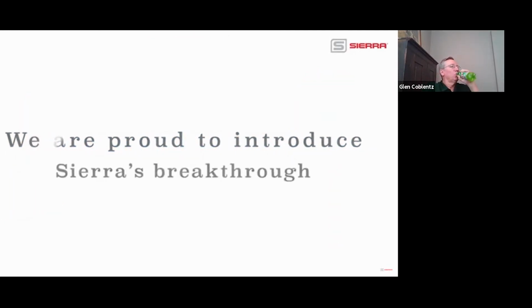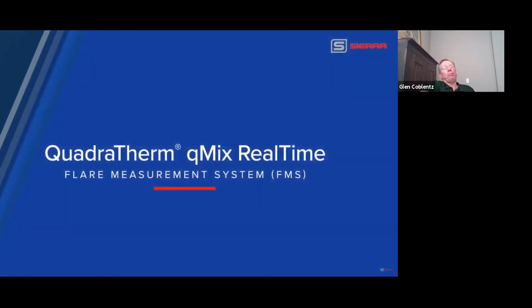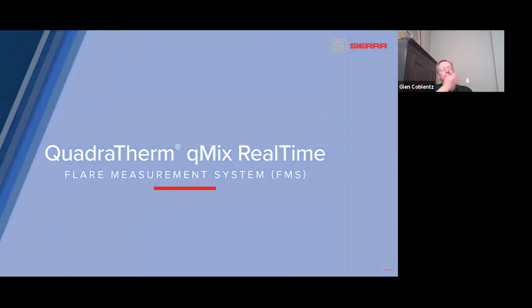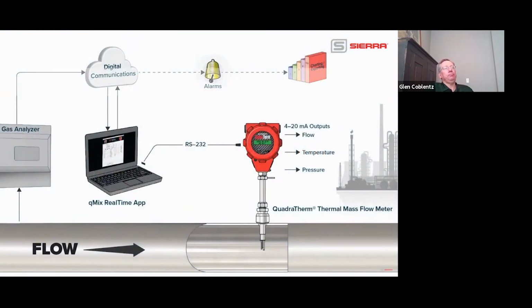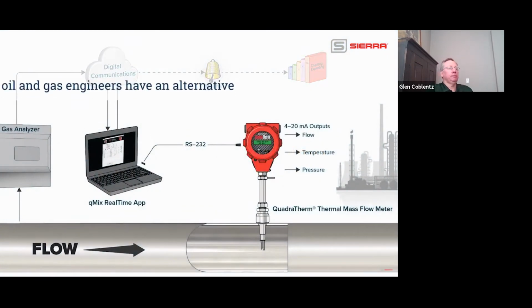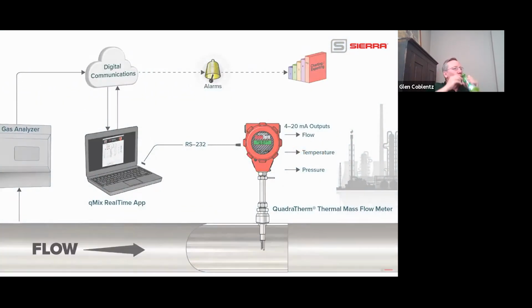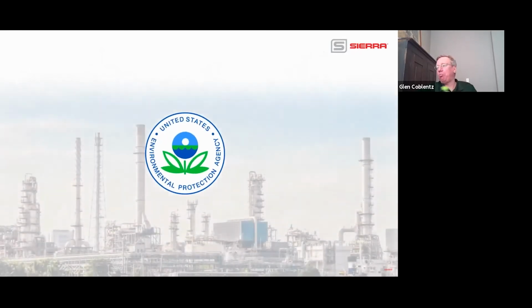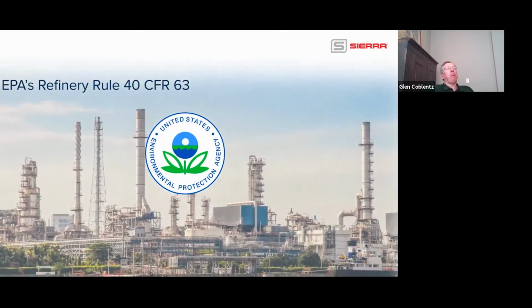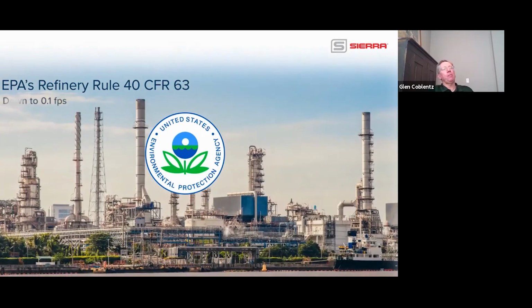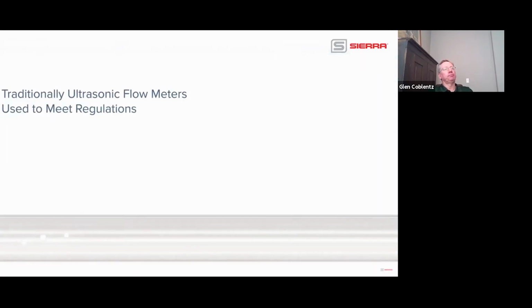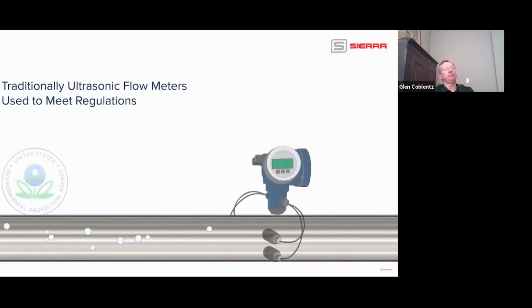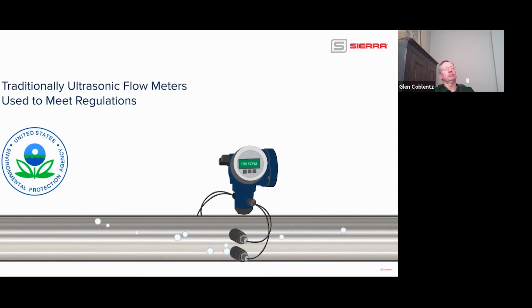Today, we are proud to introduce Sierra's breakthrough Quadratherm QMix real-time flare measurement system, FMS. For the first time, oil and gas engineers have an alternative to ultrasonic flow meters to meet the ultra-low end of EPA's Refinery Rule 40 CFR 63, which requires accurate flow measurement down to 0.1 feet per second. Traditionally, ultrasonic flow meters have been the meter of choice to meet these strict flare gas regulations.